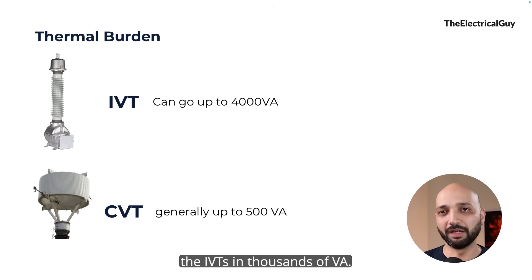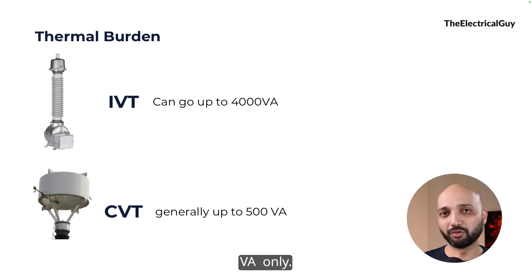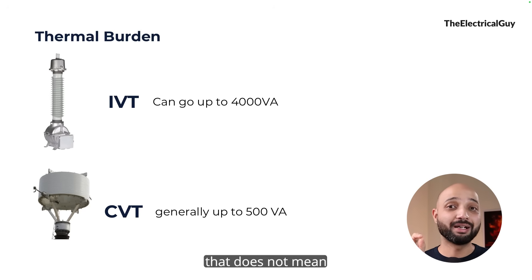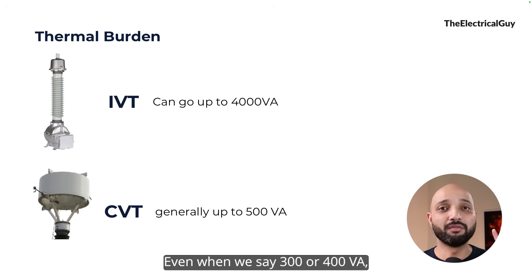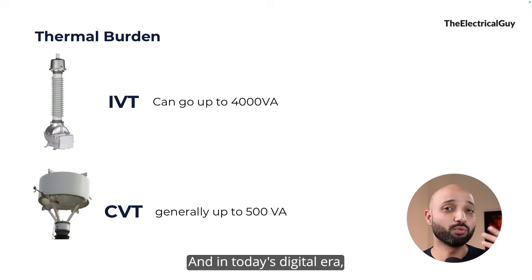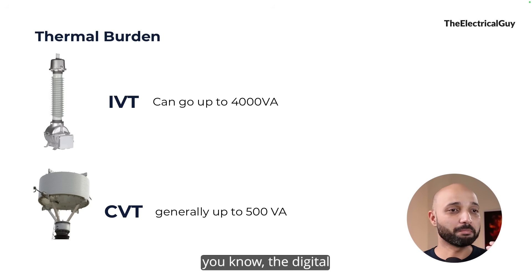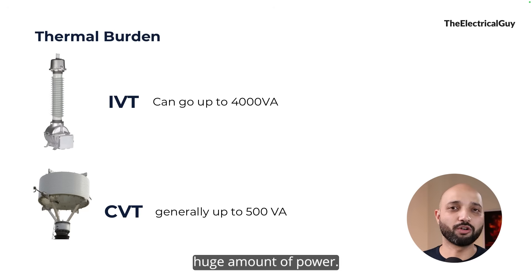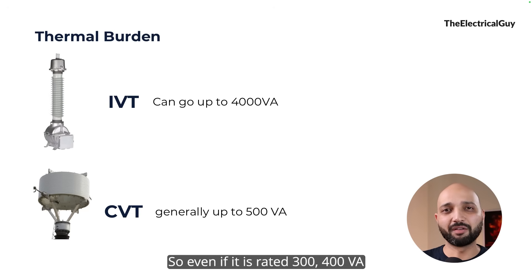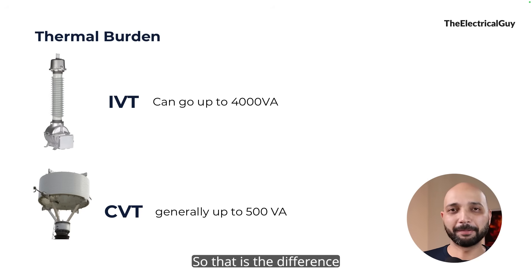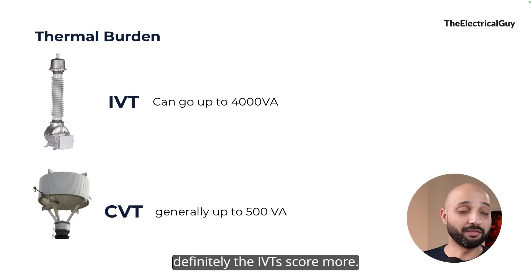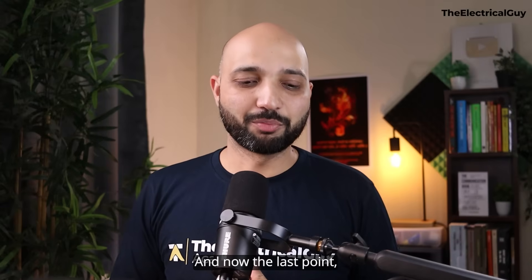Please note that a thermal burden of 300 to 400 VA from a CVT is not a limitation in practice. In today's digital era, digital relays and digital meters do not consume huge amounts of power, so 300 to 400 VA is generally sufficient. In terms of thermal burden, IVTs do score higher, but CVTs are perfectly adequate for modern applications.